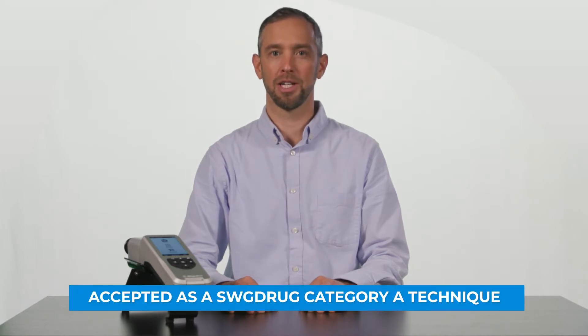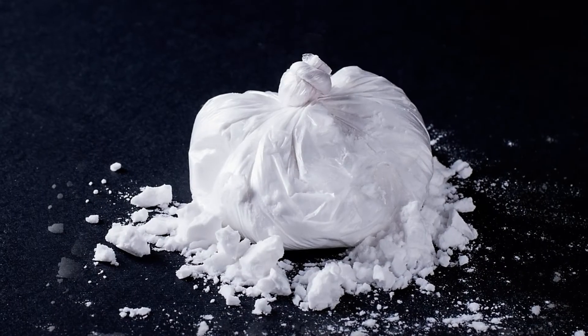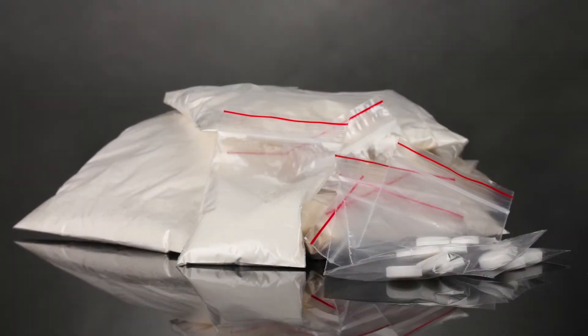The Rescue Flex is built on our time-tested and field-proven 1064 nanometer wavelength Raman engine. Accepted as a SWGDRUG category A technique, utilizing Raman means that we can provide analysis that is non-destructive, analyze a wide range of material types such as solids, liquids, powders, paste, and gels, and we can scan through translucent packaging, keeping you safe from exposure.